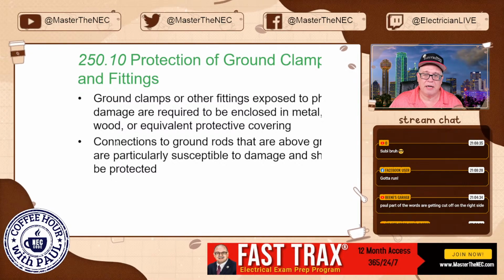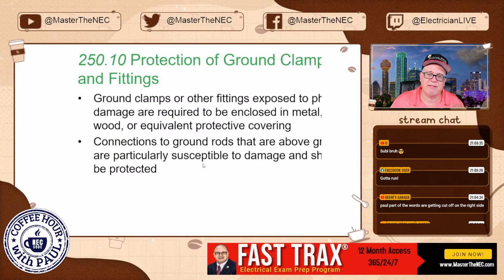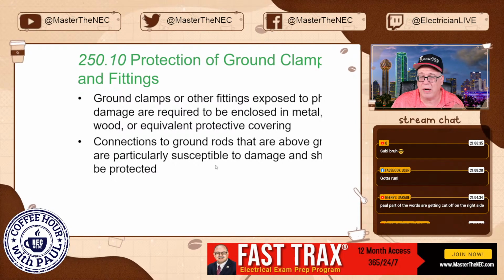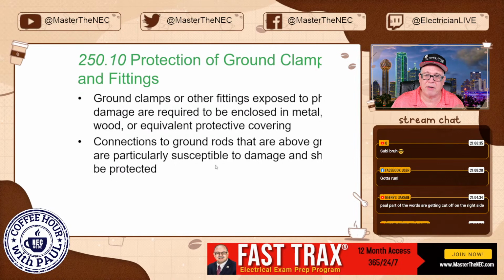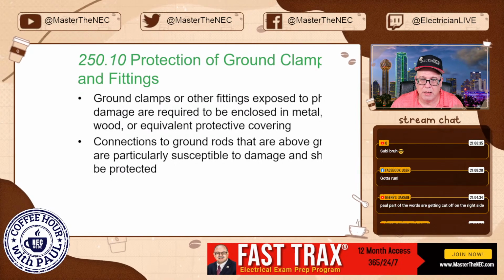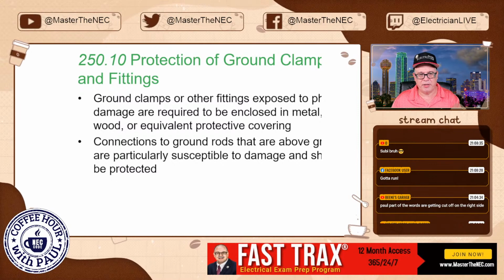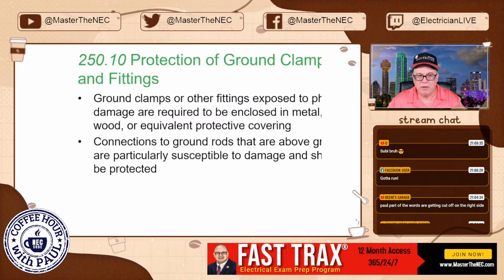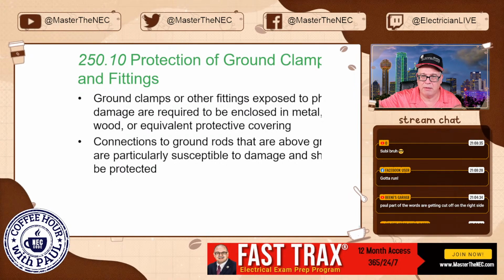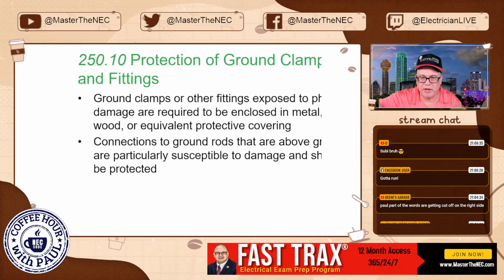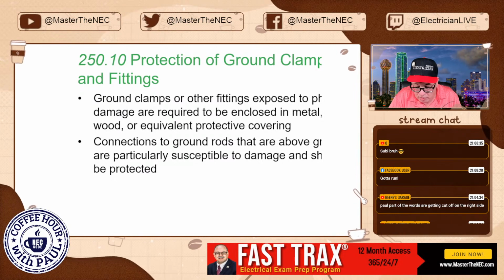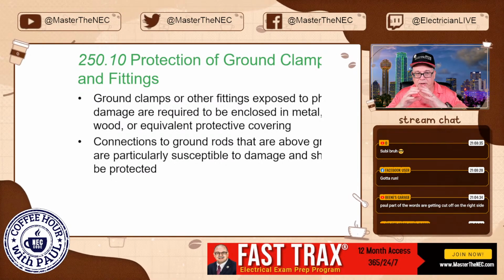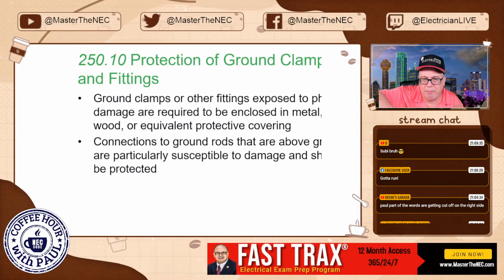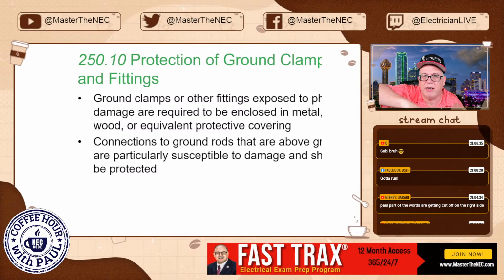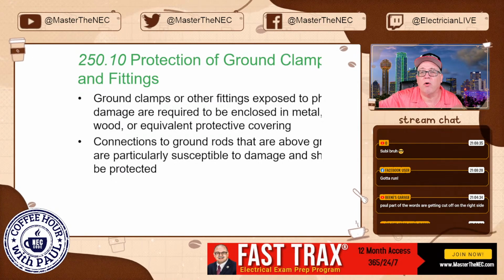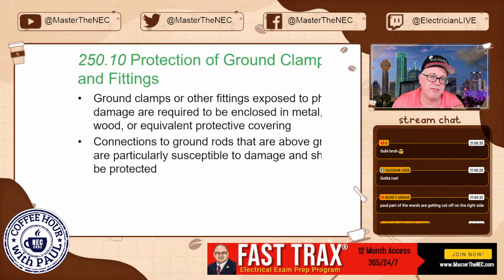Keep it below grade. Connections of ground rods that are above grade are particularly susceptible to damage and should be protected in some way. In some states, the inspectors will make you put a protective cone over it. I've seen other states where they make them put PVC over it down to a certain depth, and they'll put a plug cap on it, okay? And they'll put it in the ground, so that protects it. So you've got this ground rod, and they dig around it, and then they put a piece of PVC over it, and they glue on top of it like a clean out on the end of it. And then they put the dirt around it. So if it's going to stick out, that's a retroactive type of thing they can make you do.